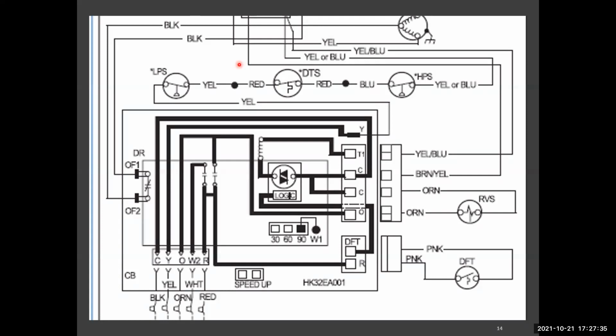Now it's going to just keep running in compressor mode until the thermostat is satisfied. We're going to start building up some frost. And then we come over here, our defrost thermostat says, hey, I'm cold enough and we should start thinking about defrost. So now we can go check, closed here for troubleshooting, and see if it sends a signal to our O. That's going to go into our triac controls, which is our controlled time logic.